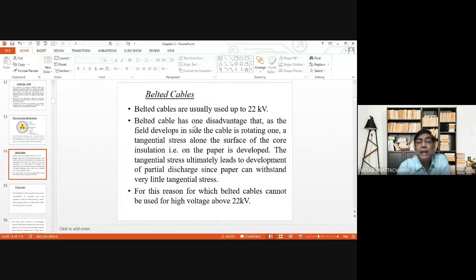Belted cable has one disadvantage: as the field develops inside the cable, three conductors are connected to three phase voltages. As a result, the electric field developed inside the cable is rotational in nature, so a rotating electric field develops, creating tangential stress along the surface of the insulation.